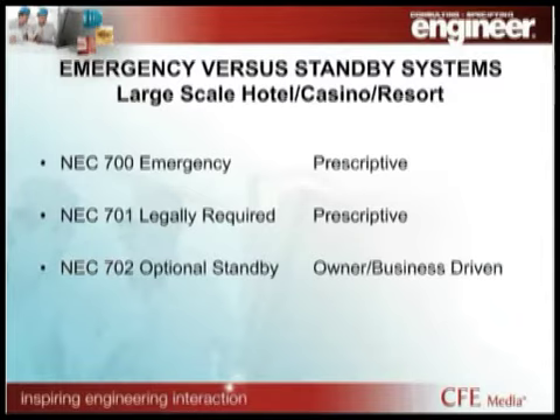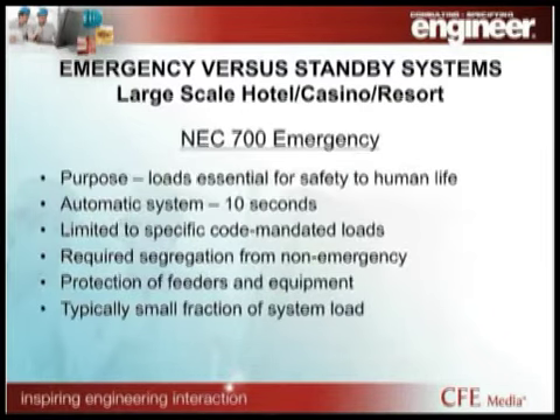When you get into optional standby systems, that's where you're really looking at what's the business need? What are we trying to protect for that owner, and what does he want to be able to maintain operations on in the event of a utility outage or failure? So if we talk about 700, again, the purpose of it is loads essential for safety to human life. That's pretty clear. It's an automatic system, so it's got to be online in 10 seconds. Again, limited to code-specific and mandated loads.